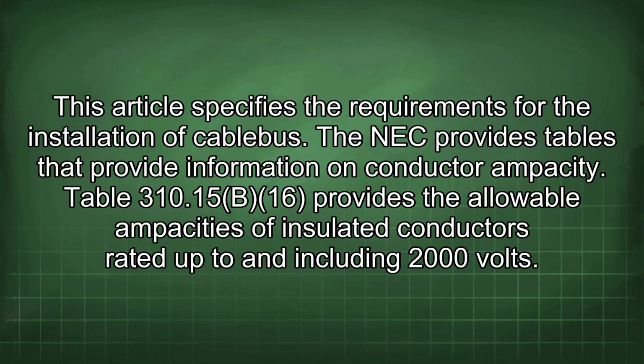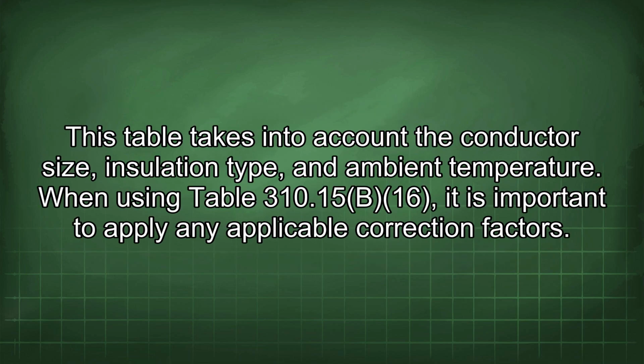The NEC provides tables that provide information on conductor ampacity. Table 310.15(B)(16) provides the allowable ampacities of insulated conductors rated up to and including 2000 volts. This table takes into account the conductor size, insulation type, and ambient temperature.